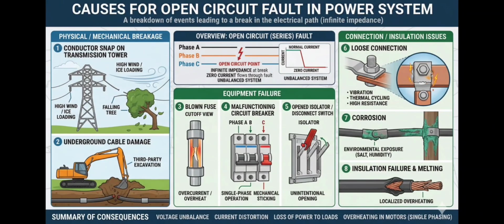How do open circuit faults happen in a power system? First, whenever a tree falls on the transmission line, the conductors will break down and the energized conductor hanging in the air will lead to an open circuit fault, and this hanging conductor should not touch the ground. If it touches the ground, it will become a short circuit fault.